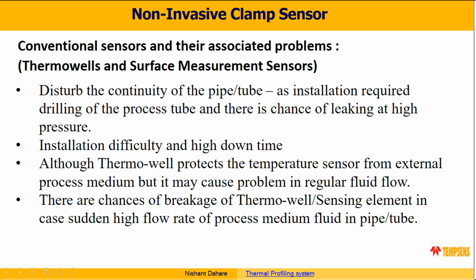With thermowells, the major problem is that it takes a lot of time to install them, causing process downtime. You have to stop the process, drill the hole, and put the thermowell inside the pipe to measure the temperature. High installation time and drilling time is required, and there are also chances of high leakage at high pressures.